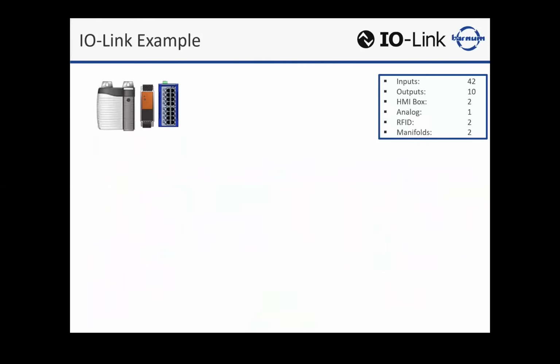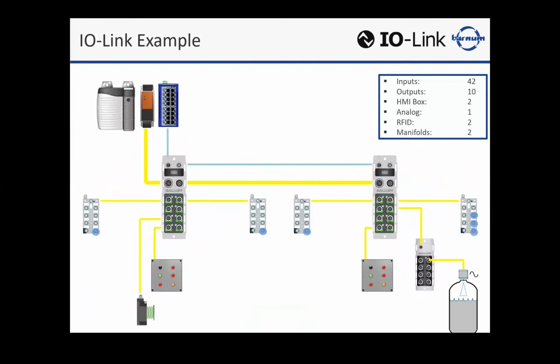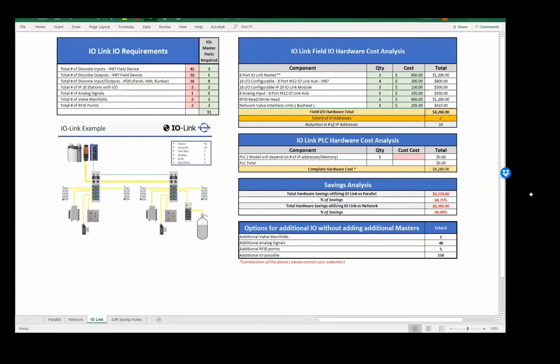But then if you can go back to the math analysis, oh, yeah, you'll see the number of IP addresses. Remember, we talked about IP addresses. So an IP address is the identity of the module that's out there. We reduced it from 16 total to 2. Now, what that means is the amount of traffic on your network. And traffic needs to be maintained, mm-hmm, to make sure you don't have devices dropping on and offline communication-wise. So that's a huge savings, one with not only the hardware you can select to use in your panel, but two, commissioning, mm-hmm, and troubleshooting in the field. When you don't have all that information smashing into each other, it can make for a much cleaner working network.